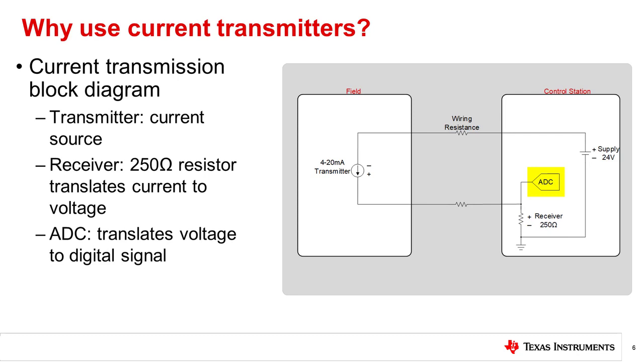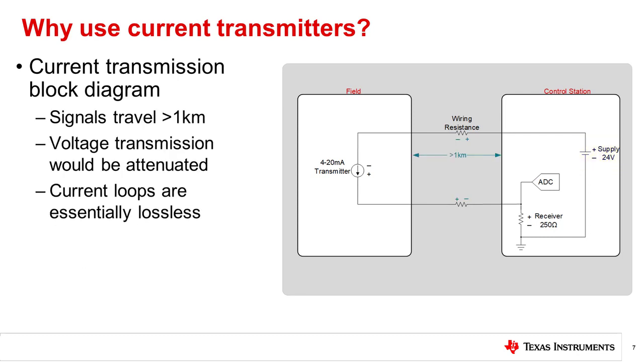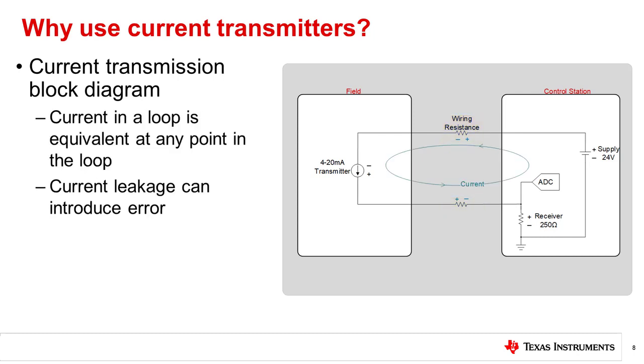The receiver in this case is a 250 ohm resistor that turns the transmitted current back into a voltage at the control station. This voltage can be translated to a digital signal for processing using an analog to digital converter. Transmission from the field sensors to control station or control station to field devices can be done with as little as two wires. The configuration in this example is a two-wire system that uses a 24-volt nominal loop supply. Sense and control signals must often travel distances of a kilometer or more. If a voltage transmission was sent over a kilometer-long wire, the voltage drops due to the impedance of the wire would cause enough attenuation to render the arriving signal unusable. 4 to 20 milliamp current loops are essentially lossless, even at long distances, since the voltage drop caused by the long transmission wires does not impact the accuracy of the current signal. Kirchhoff's current law states that the current in the loop is equivalent at any point in the loop. So if a current of 8 milliamps is read at a receiver, the current in the transmitter a kilometer away must also equal 8 milliamps. Ideally, the resistance between these two wires is infinite, but a non-ideal resistance between the wires can cause current leakage paths that add some error to the system.